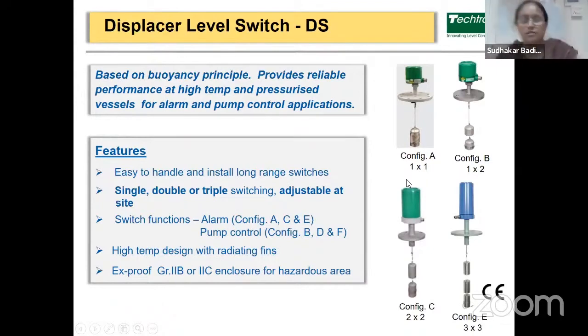Now this one is a displacer level switch. This is basically based on Archimedes' principle of submerged body, that is the buoyancy principle. It provides reliable performance at high temperature and in pressurized vessels for alarm and pump control applications. These switches are available in various configurations. On the right hand side, you can see the configuration A, that is 1x1, that is single displacer with single switch.